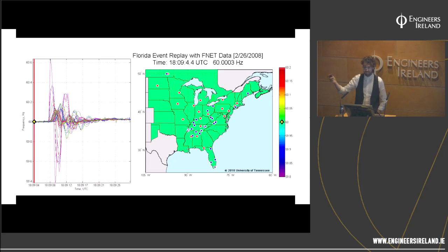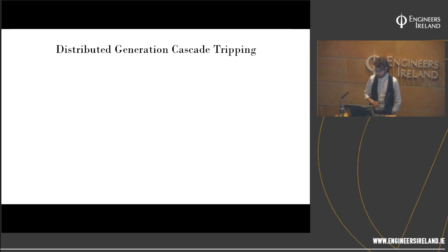But there's always unintended consequences for designs and stuff like that. So that's conventional plant tripping. Another aspect that's coming is distributed generation tripping as well from extreme frequencies. And what I mean by distributed generation is generators connected to the low voltage system, the distribution system. So that can be wind turbines, solar PV, combined heat and power. They're the main three, typically. And these generators, because they're connected on the low voltage system and they're close to you and me where we live, have protection systems that will trip in case there's an island in that region, to protect us all. But often the way they detect that island is from the rate of change of frequency that they measure, and also under and over frequency levels that they measure.